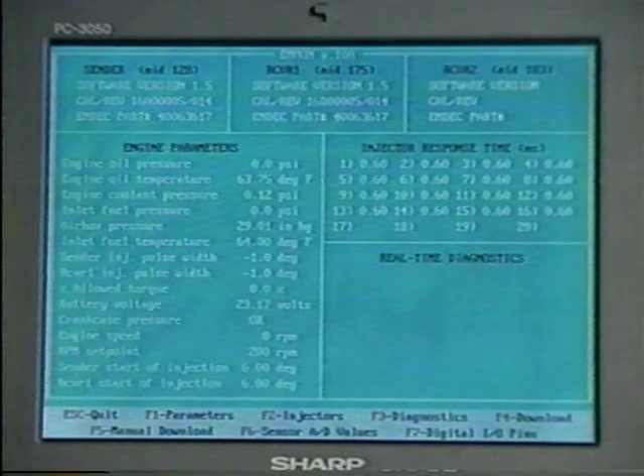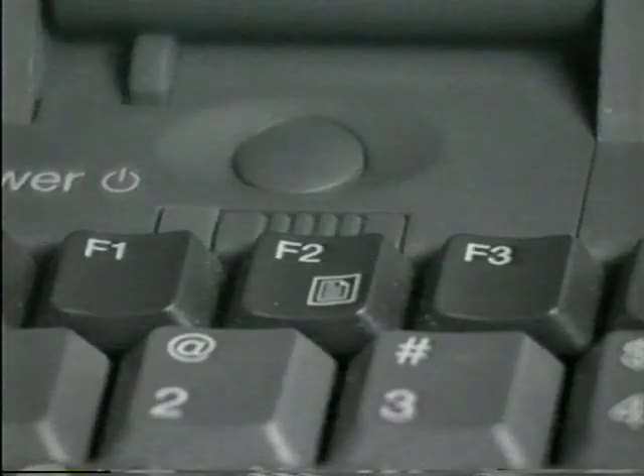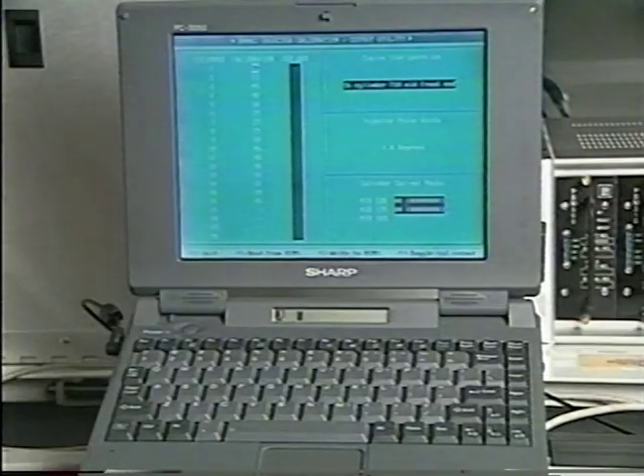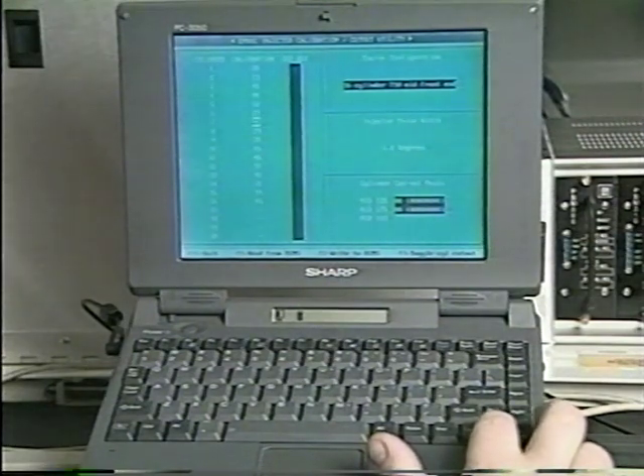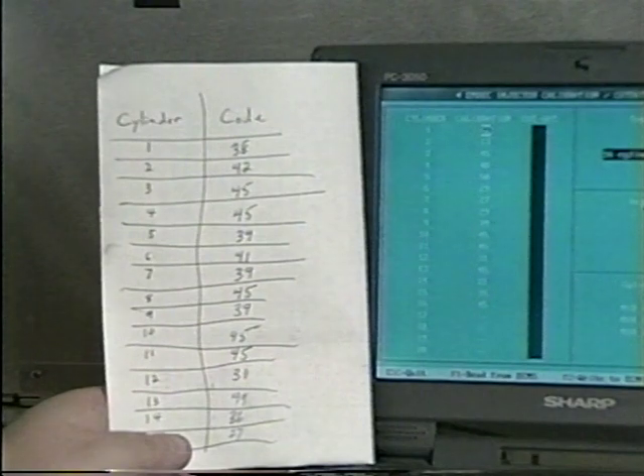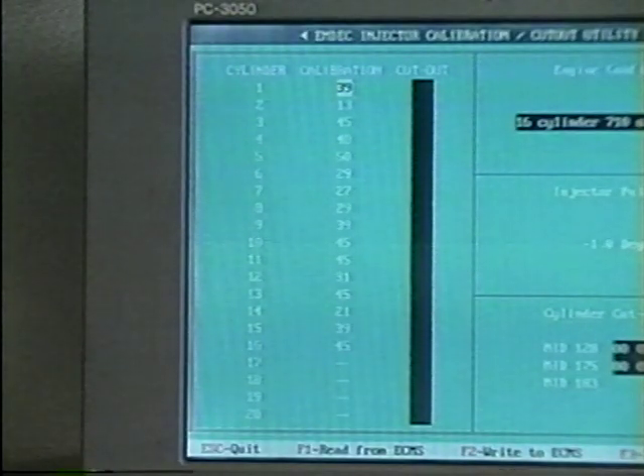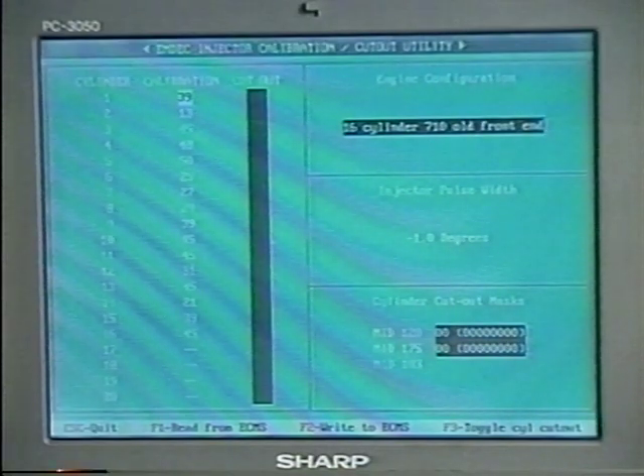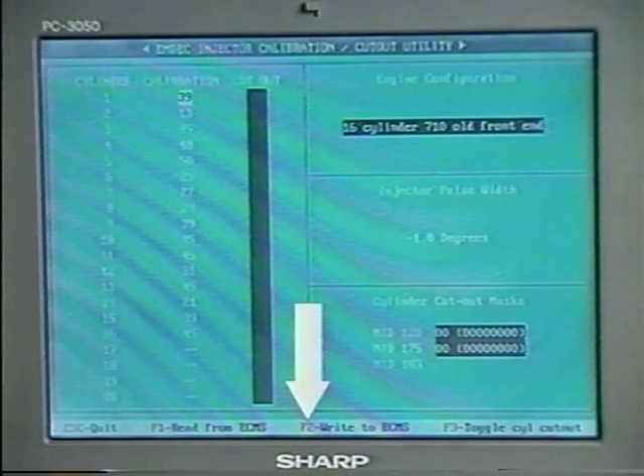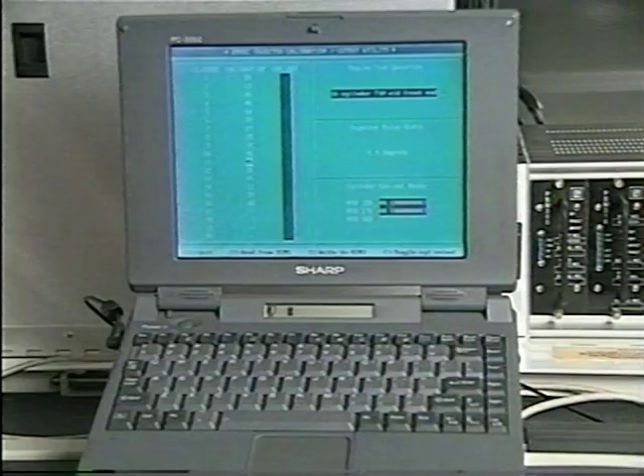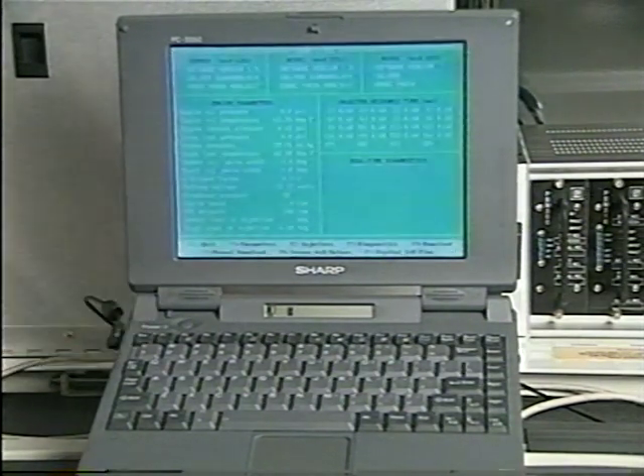From the main screen, select the function key F2, labeled Injectors. This should take you to another screen used for injector calibration and injector testing. To input the injector codes, use the up and down arrow keys to highlight the injector code you wish to modify. Simply type in the new code and proceed to the next injector. If an injector already has the correct code, it is not necessary to re-enter the code. Once all codes are entered, you now have to transmit the data to the ECMs. Select the function key labeled Write to ECMs. The revised calibration codes will now be written into the ECM's memory to complete the procedure. Press the Escape button to return to the main screen.